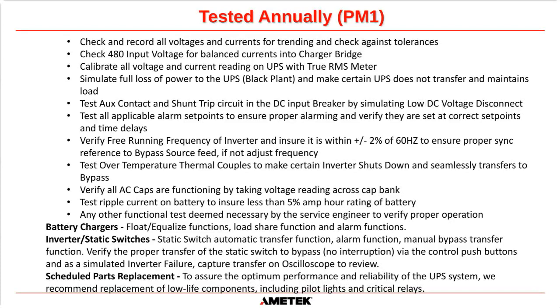So what we do to check the load share function is, let's say you have charger A and charger B, and charger A has all the current on it, then we will switch off the AC input to charger A with the current on it and make sure the current transfers over to charger B. Another way we can do it is we can just go on to charger B and press the equalize button, and that will raise the voltage of charger B to a level above charger A, and we should see the current transfer to charger B. We don't necessarily need to see the two systems share. We just need to know that they're both online and have the ability to take the load if necessary.